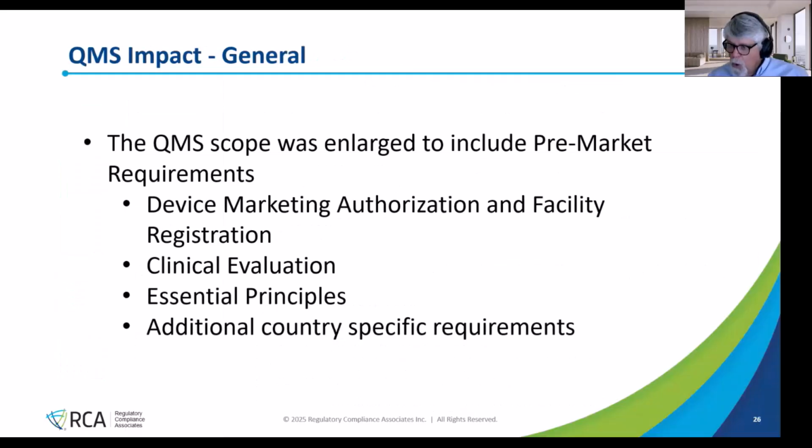What was the impact to your quality management system because of MDSAP? Here are some ideas. The QMS scope was enlarged to include pre-market requirements, device marketing authorization, facility registration, clinical evaluation, essential principles or the GSPR, and additional country-specific requirements. The device marketing authorization and facility registration regulatory stuff was not part of the quality management system before, and now it is. That includes adverse reporting and stuff. Clinical evaluation is now part of the quality management system. General safety and performance requirements, or essential principles, are now part of the quality management system.